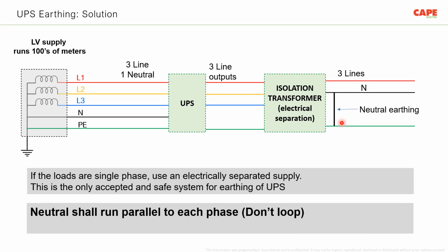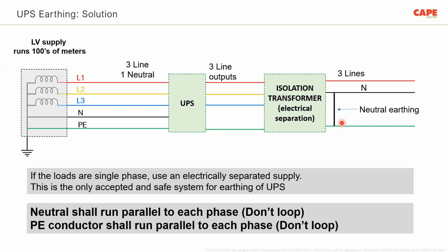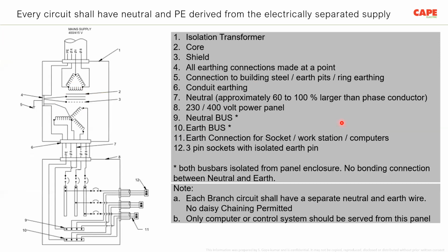And you shall not forget that the neutral shall run parallel to the phase conductor. Please don't make any daisy chain or loop it from the other circuit. The PE conductor also shall run parallel to each phase. Don't loop it from the other circuits, especially in computer loads. This particular picture which I am showing has been included in the National Building Code 2016, on how to make a wiring.